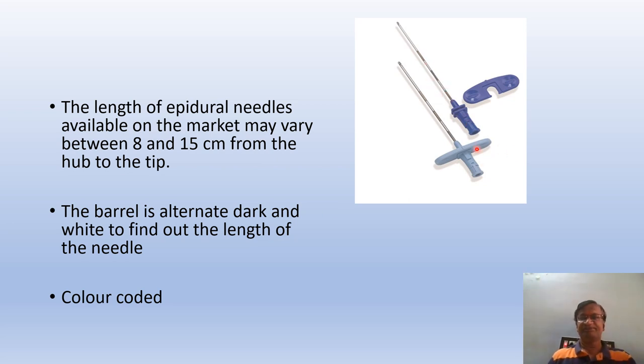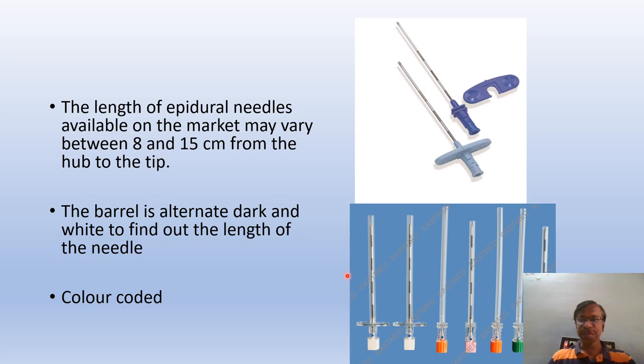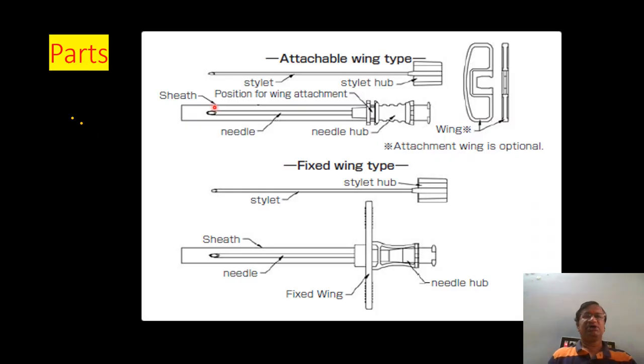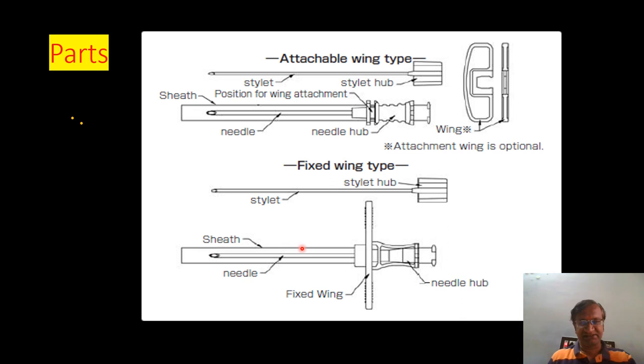It is color-coded — this is 16 gauge, this is 18 gauge. There are so many gauges available. Now here you can see: this is the Tuohy needle, inside which is the stilette and the stilette hub. There is a sheath, and with the sheath removed we have the epidural needle, which has a hub, a needle barrel, and a stilette inside. There is also a wing.